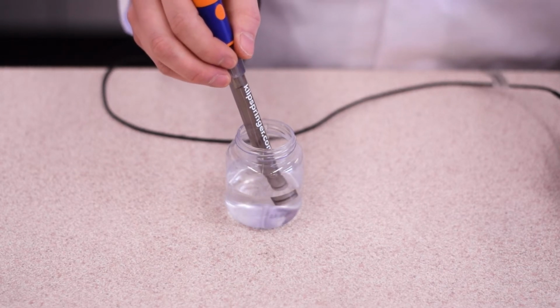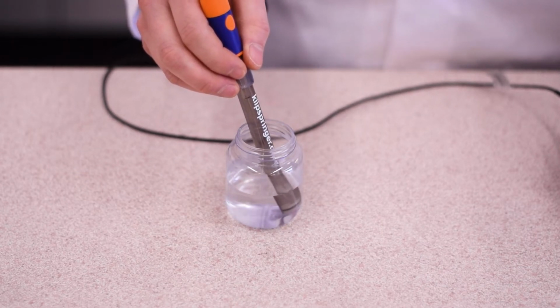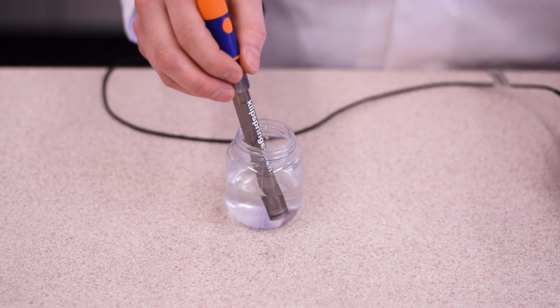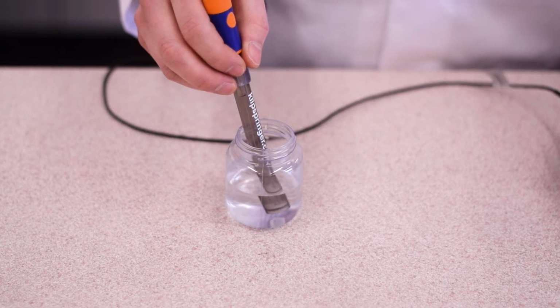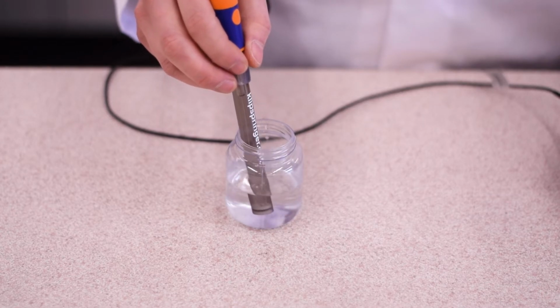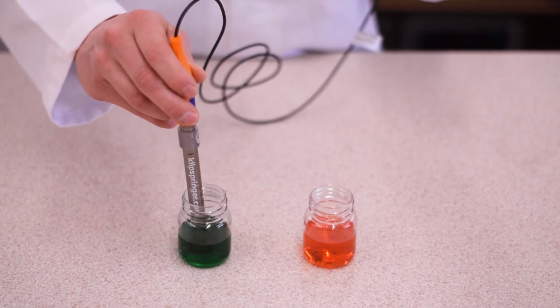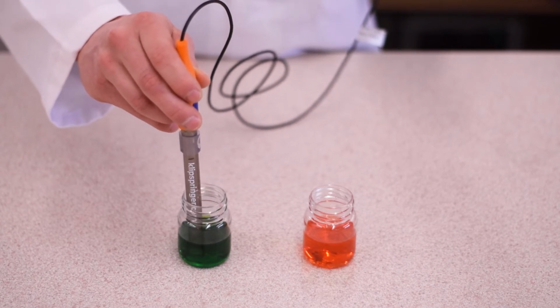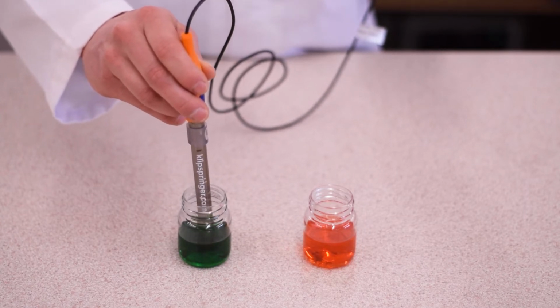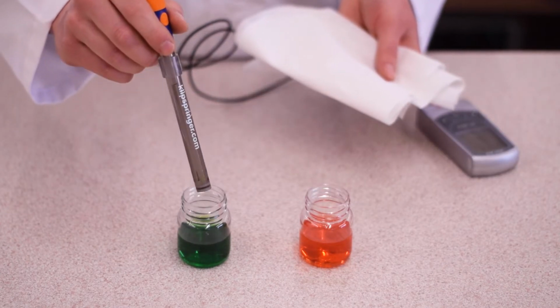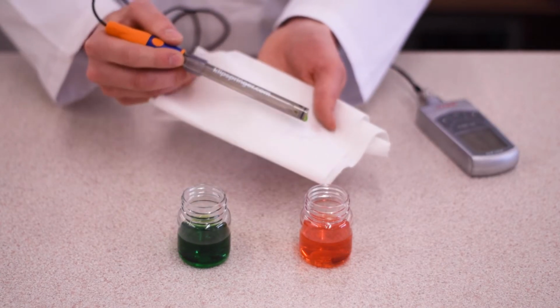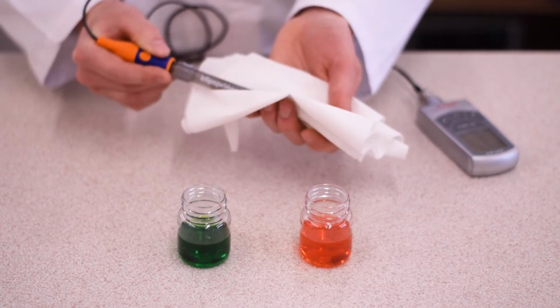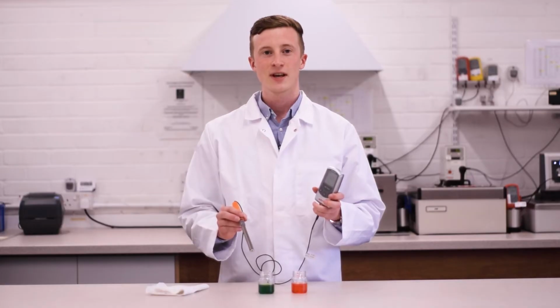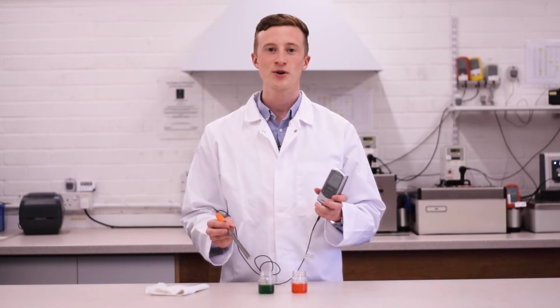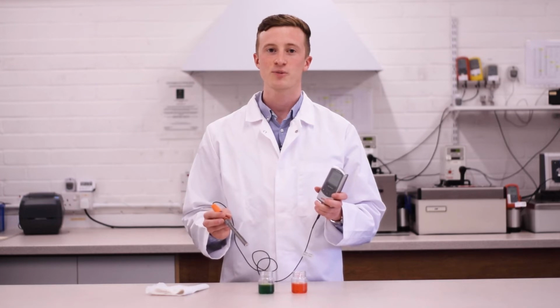Rinse the electrode in distilled water to ensure that the readings that you get from the buffer solutions are accurate and not contaminated. You may need to leave the electrode in the distilled water for around 20 to 30 seconds. Place the electrode into the second buffer solution and again press cal. Once the display has changed to OK, the calibration is complete and you can remove and dry the electrode again. The unit automatically switches to measurement mode and is ready for you to test your first product.